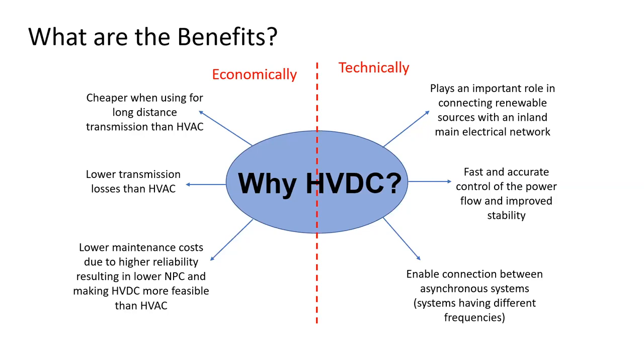HVDC also has lower maintenance cost than HVAC because of higher availability or reliability, and results in lower net present cost, which is CapEx plus OpEx, making HVDC technology more feasible than HVAC. Under technical benefits, HVDC can play an important role in connecting renewable power with an inland existing grid. HVDC can also control power flow at a faster rate than HVAC, which can improve stability.